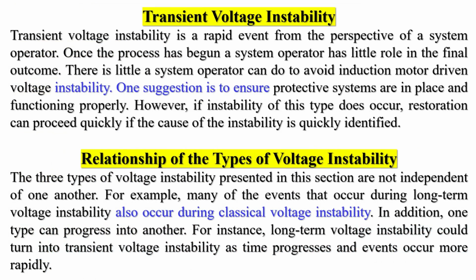Transient voltage instability. Transient voltage instability is a rapid event from the perspective of a system operator. Once the process has begun, a system operator has little role in the final outcome. There is little a system operator can do to avoid induction motor-driven voltage instability. One suggestion is to ensure protective systems are in place and functioning properly. However, if instability of this type does occur, restoration can proceed quickly if the cause of the instability is quickly identified.